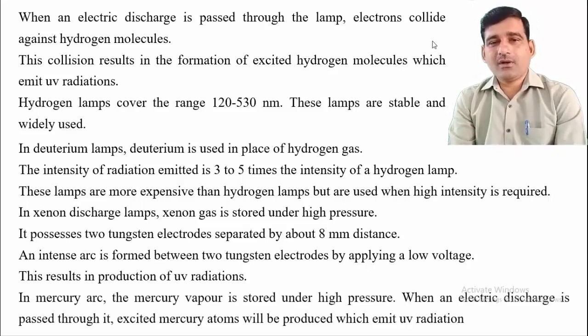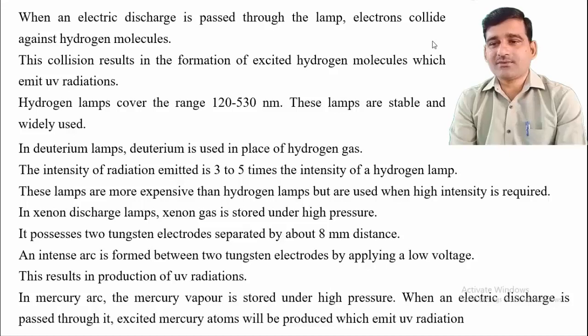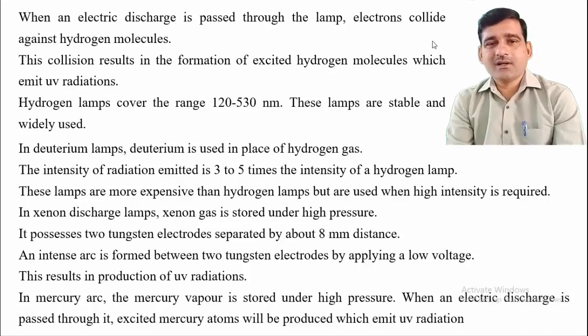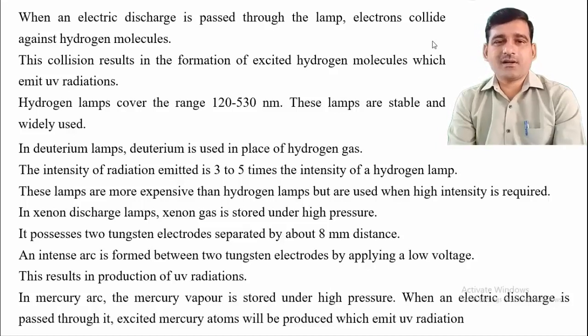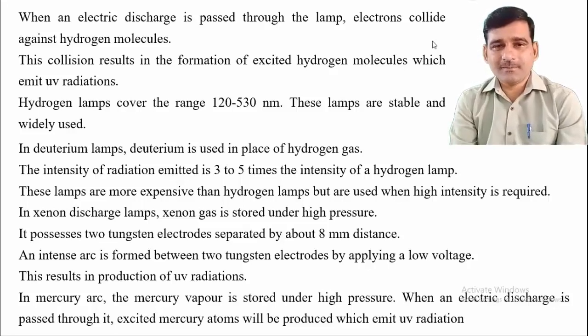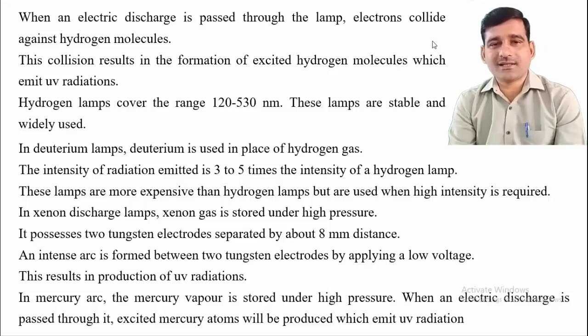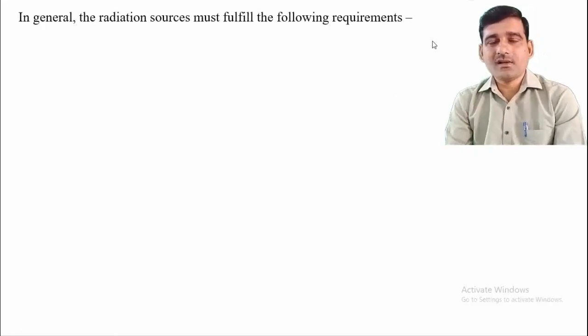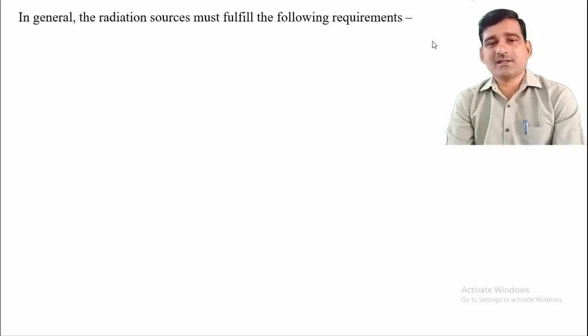In a mercury arc lamp, mercury vapor is stored under high pressure. When an electric discharge is passed through it, excited mercury atoms are produced which emit radiation in the ultraviolet region. In summary, for hydrogen, deuterium, xenon discharge, and mercury arc lamps, the gas vapors are stored in an evacuated glass bulb. Applying power supply causes electron collisions, exciting the gas, which then returns to ground state by emitting light in the UV region.